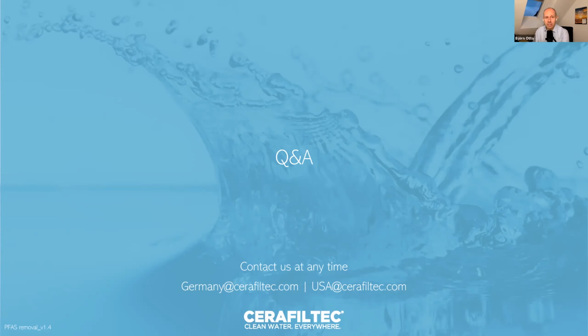Okay. Piyush was asking the question about the specification of the PAC. Can you say something about this? Can you restate that? The specification of the powder carbon. Oh, the powdered activated carbon. Yeah. We actually used a Hydro Darco S51, which is a washed carbon. We also experimented separately with an unwashed carbon that they provided. They're very gracious in giving us lots of samples to use and test the effectiveness. But we stuck with the Hydro Darco and the S51 for this test. But we've been successful with several other manufacturers as well.